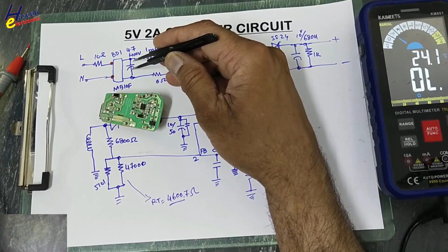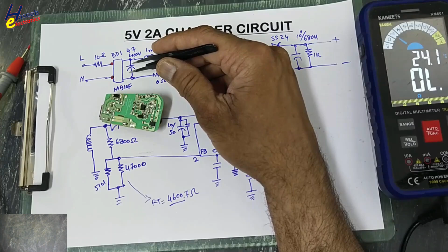If the same 220 volt AC gives only 220 volt DC here, that means this capacitor is open circuit from inside. It is not maintaining the peak voltage, it is only taking the RMS rectified voltage. In that case we need to replace these capacitors.